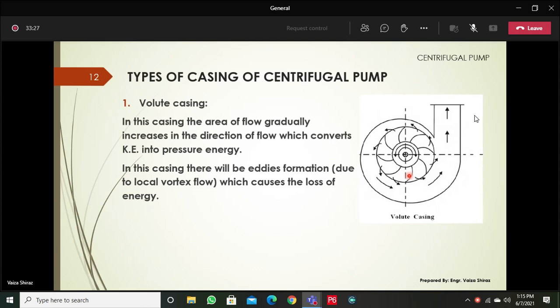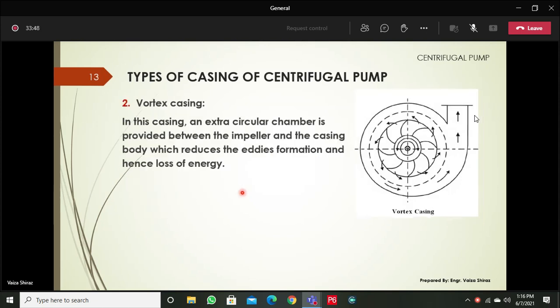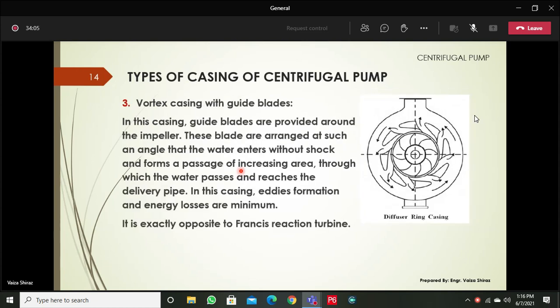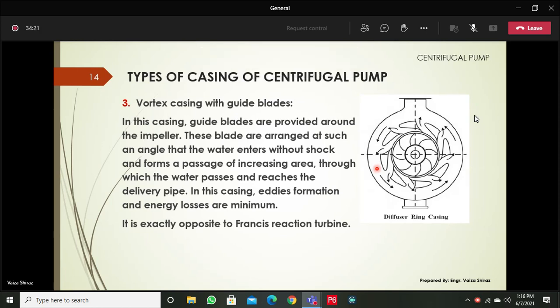There are different types of casing for the centrifugal pump. The first type is the volute casing, where the flow area is not uniform along the flow direction, causing eddy formation and loss of energy. The next is the vortex casing, where an extra circular chamber is provided between the impeller and the casing to reduce eddy formation and energy loss. The third type is the vortex casing with guide blades, which is the most efficient — it properly guides water from the impeller toward the casing with minimum losses, and is exactly opposite in layout to the Francis reaction turbine.